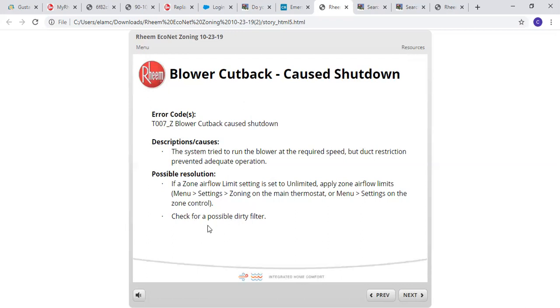Another thing is check for possible dirty filter. That will cause it. If you have somebody that's shutting vents down, shutting supply registers down, or blocking returns, that will also cause the same thing. And you can actually verify your static pressure by going on your main thermostat, going to service, and then status, and then going to your air unit, whether it's furnace or air handler. Go to your furnace or air handler. On the left hand, 4 down, it will tell you what your static pressure is.